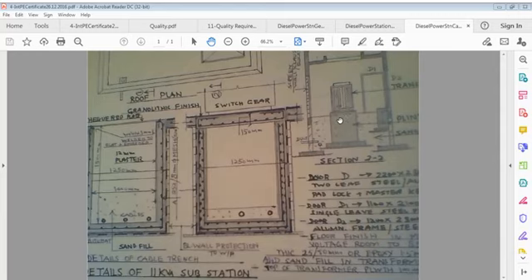You may see the substation, and this is a roof plan which I'll show separately. These are cable trenches, RCC, sized 125 by 1250, with detailing of the isolation arrangement. In some cases there is an RCC cover, in others checkered plates, with 12 mm plaster inside, and flats of 40 by 40 by 3 mm for the checkered plate case.